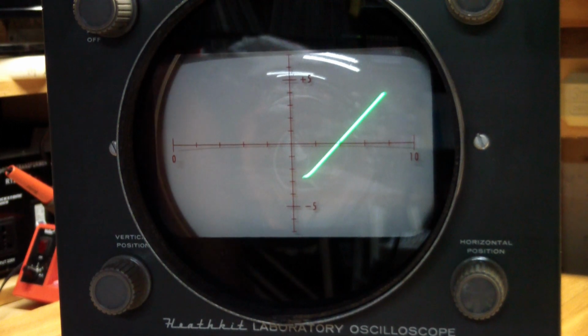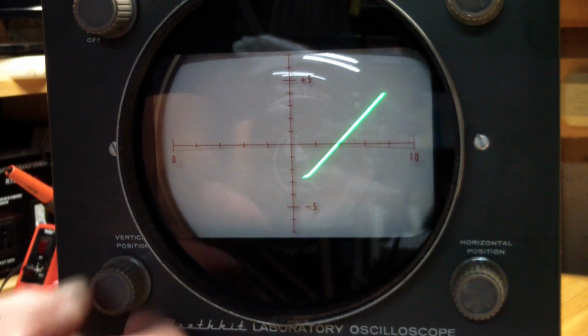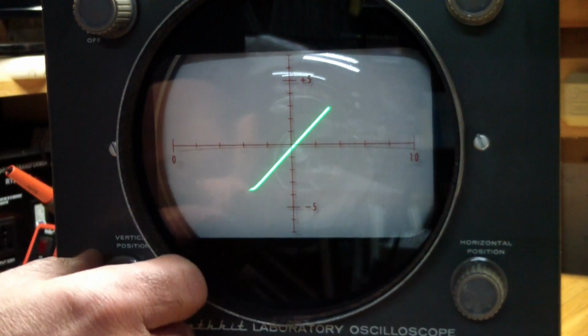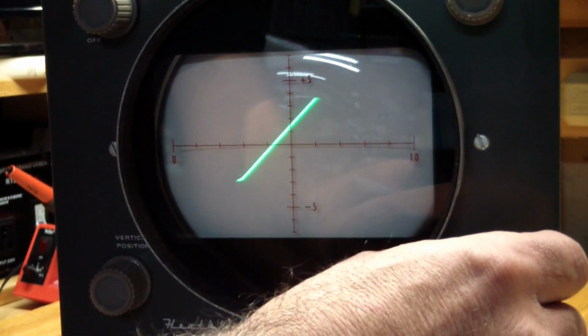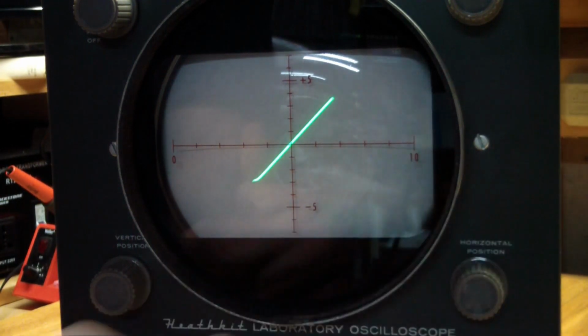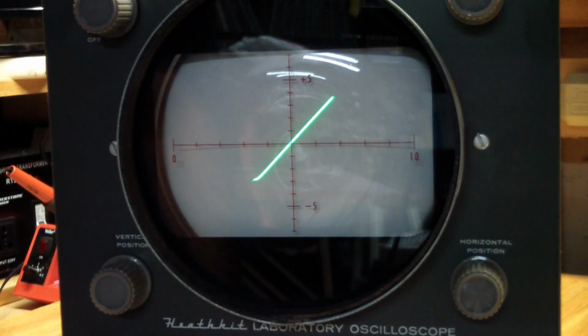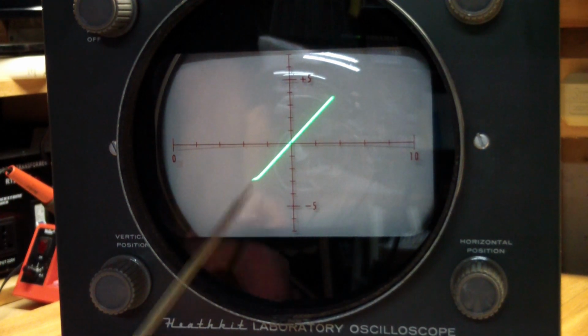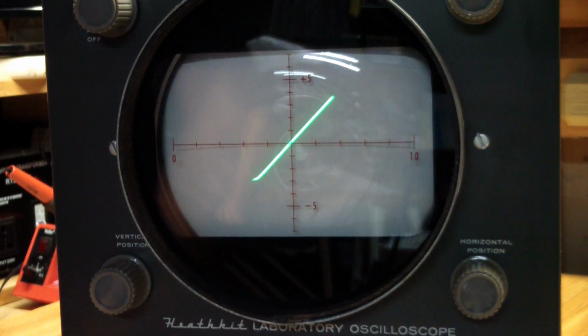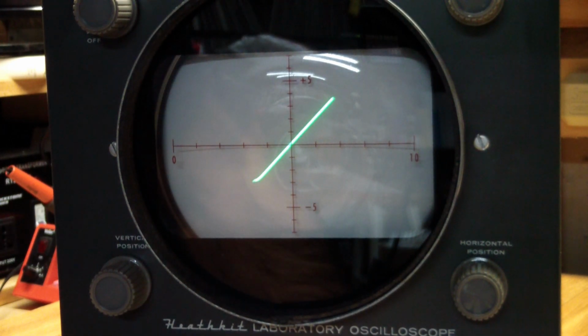Next we feed the horizontal output, which is essentially the sweep, into the vertical input, and as expected it gives us a line at roughly a 45-degree angle. And then we position it so it is centered about the origin. It's a little bit too high, but not exactly. And this adjustment is for getting rid of the little bend at the end of the trace over here. Thankfully this does have a trim pot for that.